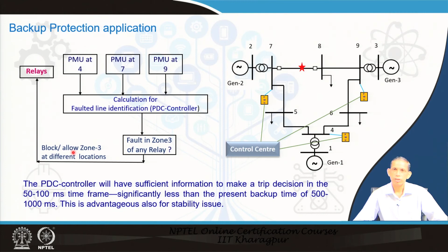So, that will speed up the process of decision, because it will be able to know that it is a decision of zone 3, zone 1 is not operating. So, therefore, you can say that zone 2 is not operating, there is a failure. So, it can go for the protection decision at a faster rate. Thus we see that PMU data can be used as a backup arrangement, as a supplementary arrangement to the zone 3 protection perspective, which seems to be compatible from latency issue also.